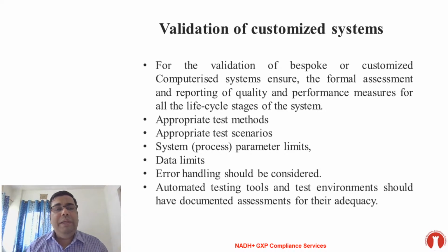So many companies do not consider negative challenge, and FDA and other inspectors of course are more interested in negative challenges because they want to understand what can go wrong with your system. Everybody should focus on this when you are thinking about your computer system: what can go wrong with this system? So always remember to consider that type of test methods.